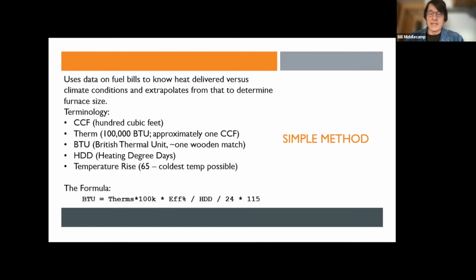And then this last number is a funny little number. It is the temperature rise. So for example, if the temperature is 30 degrees, you want the temperature rise to be 35 degrees to bring it up to that heating degree level. I used -50 as the coldest possible temperature I could possibly imagine ever happening in the Twin Cities. And so I came up with a temperature rise number of 115 degrees.